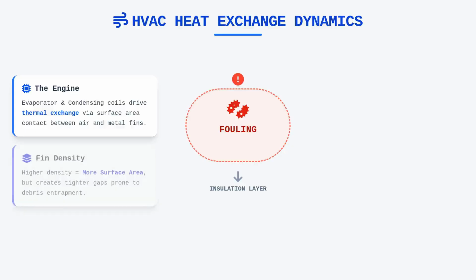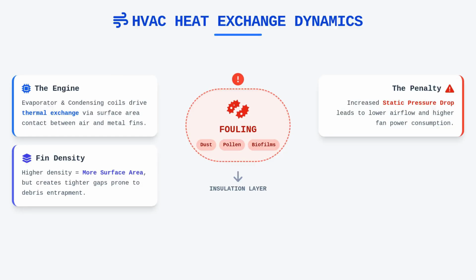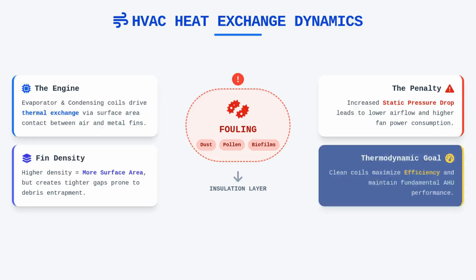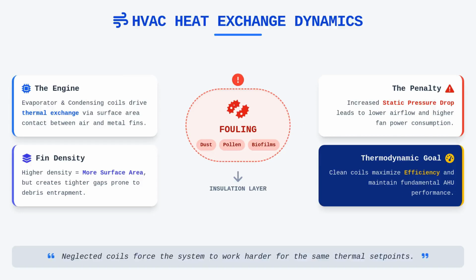Fin density is a critical design factor here, as higher density creates more surface area, but also creates tighter gaps that easily trap debris and foster microbial growth. When coils become occluded with dust, pollen, or biological biofilms, the static pressure drop increases, which directly impacts the airflow volume and the fan's power consumption. Maintaining clean coils is therefore not just about indoor air quality, but about the fundamental thermodynamic efficiency of the entire air handling unit.